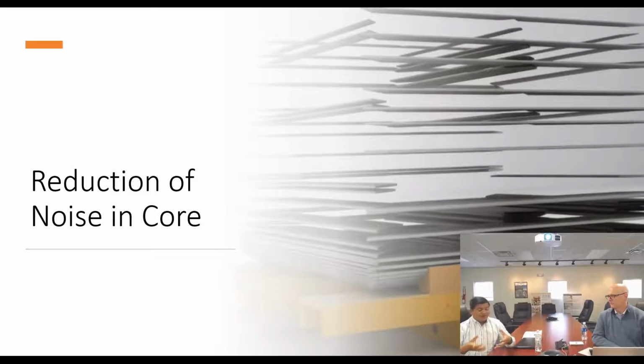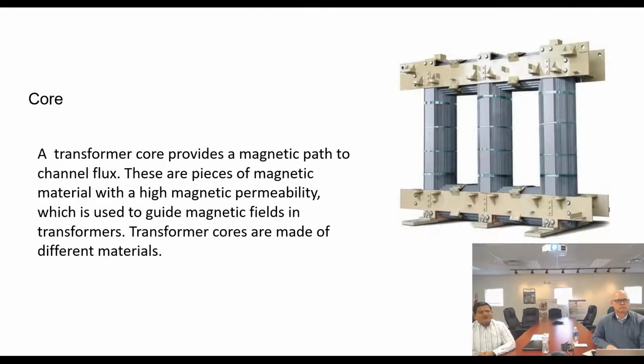Now, as we talk about what amount of noise would be generated, let's discuss how to reduce that noise. We'll start with the first thing, the core. The core provides the magnetic path or channel for the flux, and these are steel, a magnetic material with high magnetic permeability. As I explained earlier, these are specially made steel with a layer of silicon on both sides, so that every sheet is individual in the construction of the core, and that gives you the magnetic path with high permeability for the transformer. Transformer cores are made with different grades of material. The basic construction is the same, CRGO, cold rolled grain oriented steel. However, there are different grades of that, and based on the higher grade of material, we get a higher permeability.